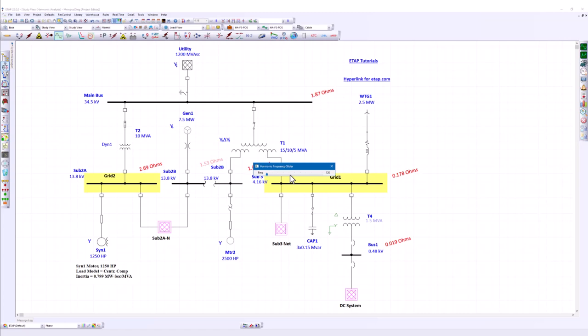Instead of showing harmonic orders 1, 2, 3, 4, it shows all the harmonic frequencies that's specified in the study case. Under each harmonic frequency, you will notice an impedance value shows at the corner of each bus. This represents the bus driving point impedance. And this data can be used to determine where are the possible parallel resonance frequencies.